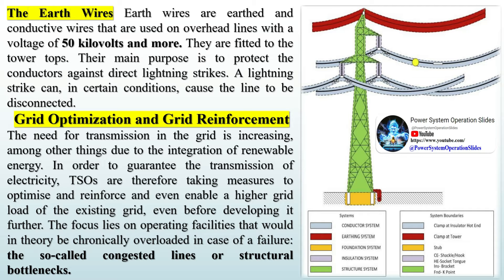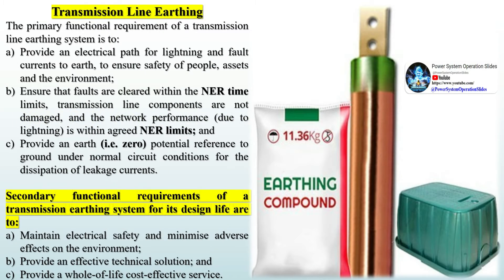The need for transmission in the grid is increasing, among other things due to the integration of renewable energy. The focus lies on operating facilities that would in theory be chronically overloaded in case of a failure — the so-called congested lines or structural bottlenecks. The primary functional requirement of a transmission line earthing system is to provide an electrical path for lightning and fault currents to earth, to ensure safety of people, assets, and the environment, and to ensure that faults are cleared within the NER time limits.